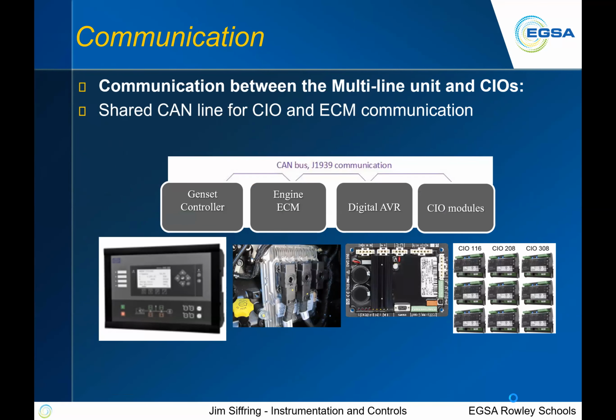And then we also get communication. Again, the J1939 is going to be the bus that all these things communicate over. So here's the genset controller. Then you got the ECM that's on there. The voltage regulator is tied into that. There may be other CIO custom input output modules that tie into that. Maybe something is controlling airflow or controlling a fan or other things like that.